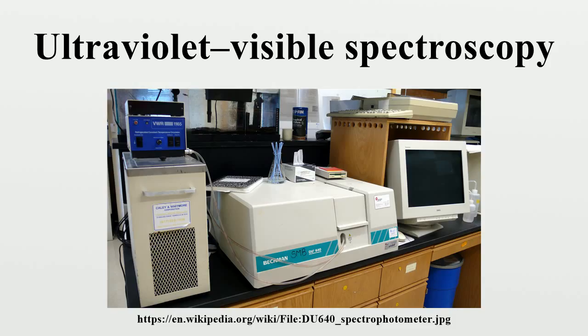Some double-beam instruments have two detectors, and the sample and reference beam are measured at the same time. In other instruments, the two beams pass through a beam chopper which blocks one beam at a time. The detector alternates between measuring the sample beam and the reference beam in synchronism with the chopper. There may also be one or more dark intervals in the chopper cycle, in which case the measured beam intensities may be corrected by subtracting the intensity measured in the dark interval before the ratio is taken. Samples for UV-Vis spectrophotometry are most often liquids, although the absorbance of gases and even of solids can also be measured. Samples are typically placed in a transparent cell known as a cuvette. Cuvettes are typically rectangular in shape, commonly with an internal width of 1 cm.